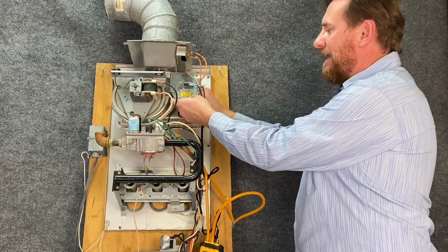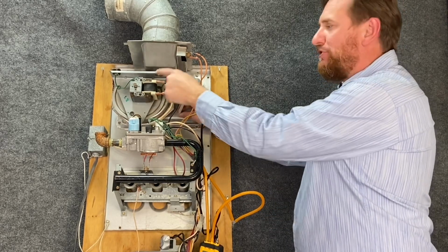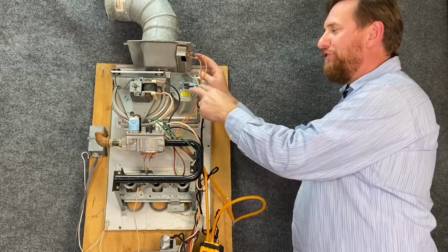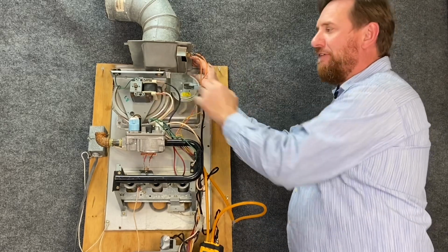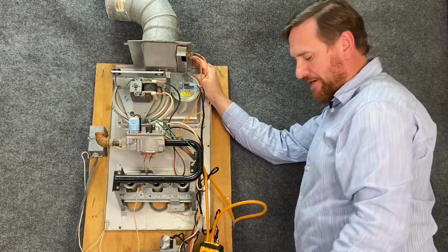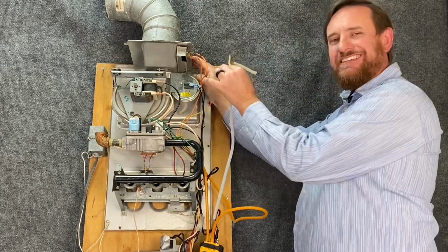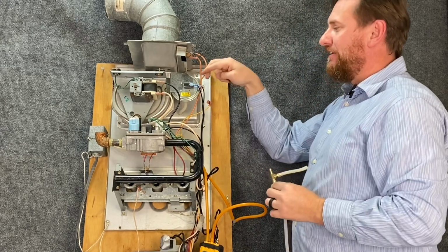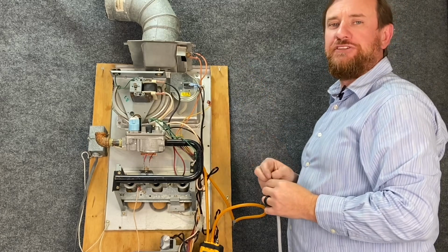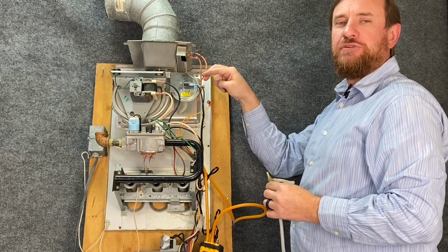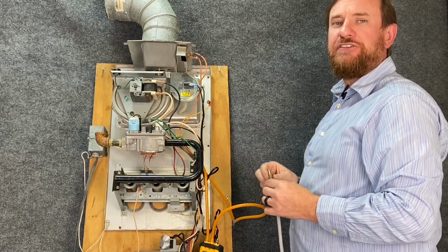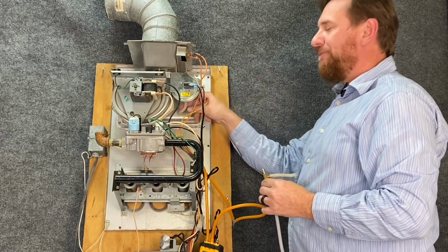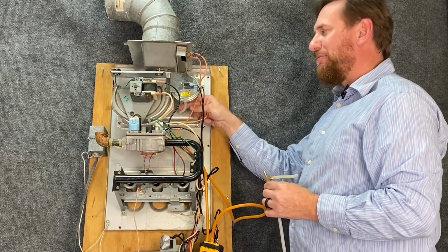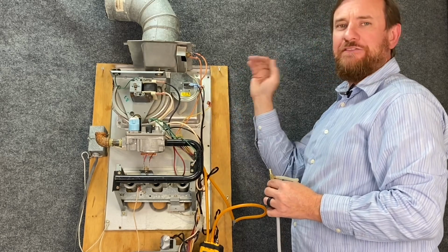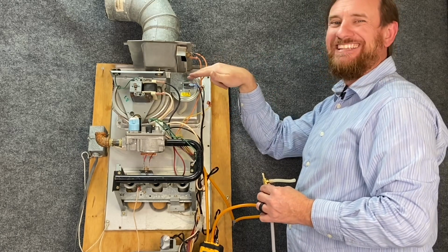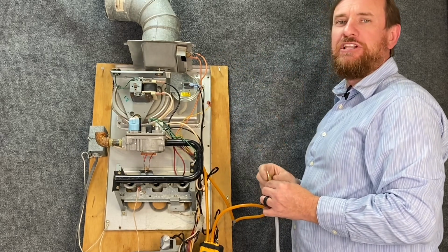So just to recap, it's a safety device that makes sure this fan motor is working. Most of them are normally open. They close when we have the proper vacuum. To test it, the method I prefer is a T and a manometer, and check to see if the switch is open or closed with voltage. If I'm reading 24 volts, the switch is open. If I'm reading 0 volts, the switch closed. Very simple. Don't suck on it. Don't pull too much pressure on it. You don't want to damage it. And if you have to replace it, go back to make sure it has the exact same inches of water column that it closes for.